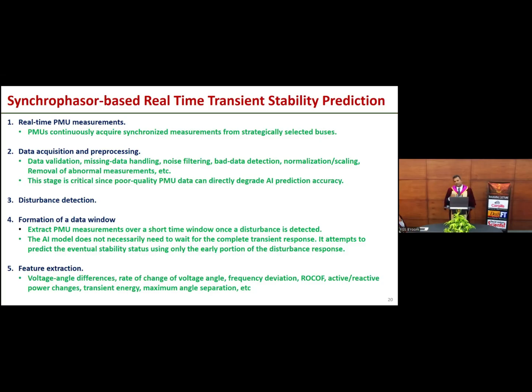When it comes to transient stability prediction, the output of the algorithm is a 1-0 kind of answer, whether yes or no. If really needed, we can further modify it to give the number of generators which are unstable, which generator, and the stability margin, depending on how complex your algorithm is. If it is oscillatory stability assessment, we process this data to get the damping ratio, which is a key parameter in oscillatory stability assessment in power systems.